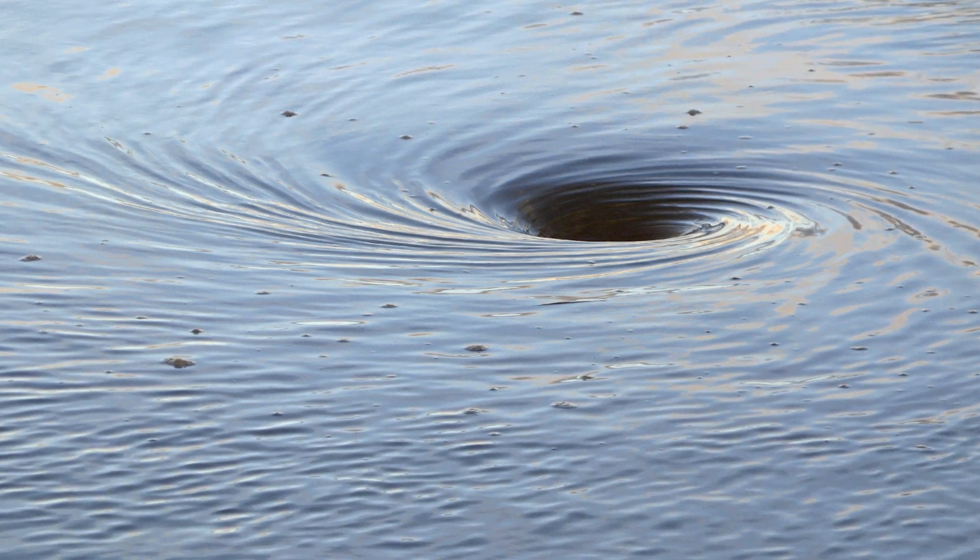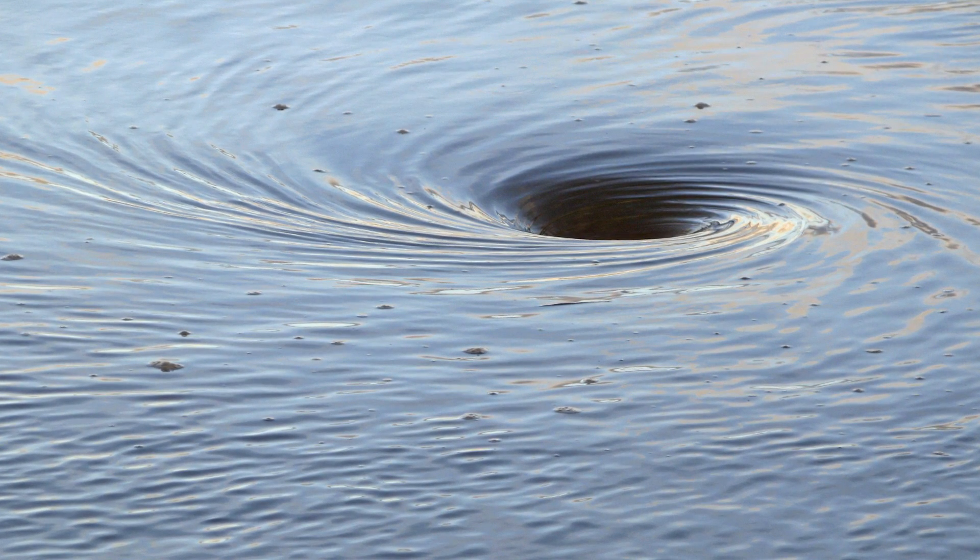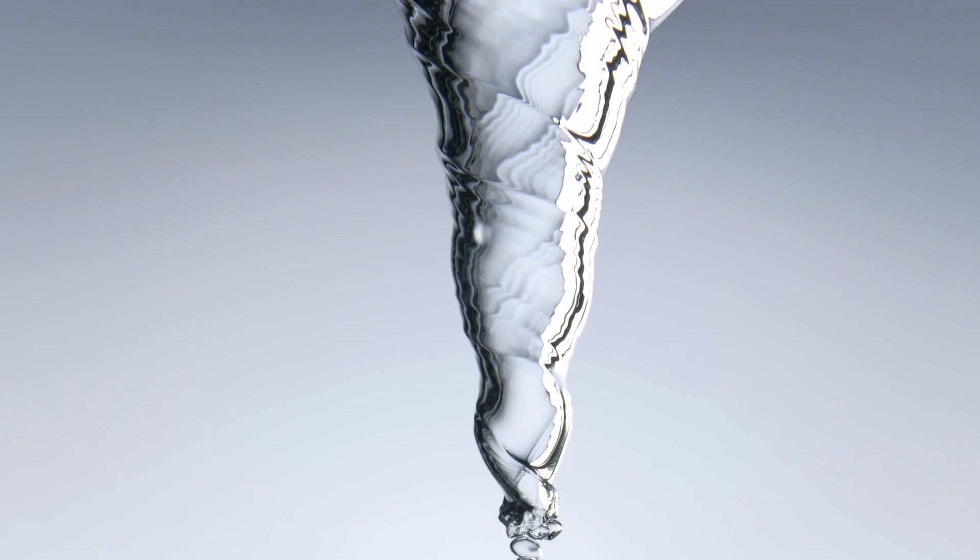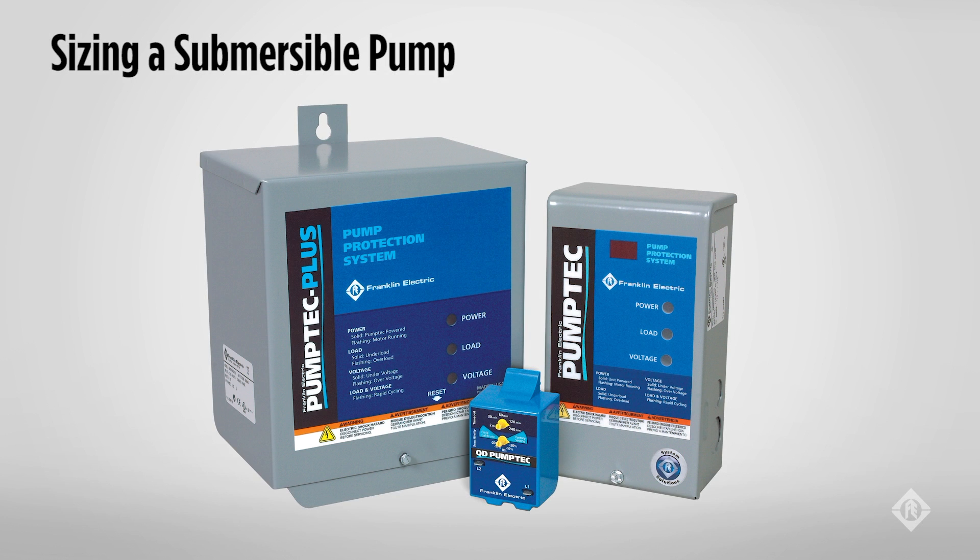Submersible pumps can only lose prime if they vortex, suck air from the surface of the water to the intake, or pump the water down to the intake of the pump, causing the pump to lose prime either way. If a submersible pump loses prime, it will run until it's either turned off by a control or destroys itself from heat.